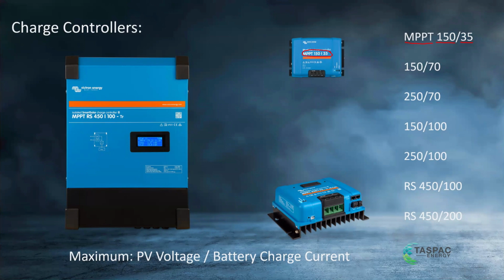Normally it's 2 or 3 panels, depending on the open circuit voltage of your panels. And this is how much current I'm going to get into the battery, 35 amps. So if you want to figure that out, you go, what's 35 amps times my battery voltage equals watts. In this case, if you've got a lithium battery, you could say your battery voltage is 52. Or if I make it easy, say 50 volts, 35 amps times 50 volts, that's somewhere around 1800 watts, right? So it's about 1.8 kilowatts of solar charging capability. So you could put 2 kilowatts on there, 3 kilowatts maybe. Don't over PV them too much, but they work pretty hard, these little charge controllers.